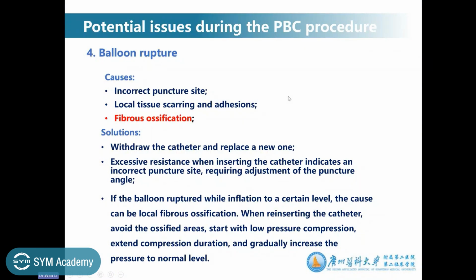Balloon rupture we can sometimes also meet. It is always induced by an incorrect puncture site or local tissue scarring and adhesion, fibrous ossification. The solution is to withdraw the catheter and replace it with a new one. Excessive resistance when inserting the catheter indicates an incorrect puncture site, requiring adjustment of the puncture angle. If a balloon ruptures when inflated to a certain level, the cause can be local fibrous ossification. When reinserting the catheter, avoid ossified areas, start with low pressure compression, extend compression duration, and gradually increase the pressure to the normal level.